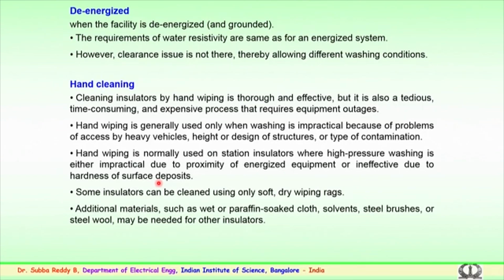So, hand wiping is generally used only when washing is impractical because of problems of access by heavy vehicles, or because of the height or design of a particular structure, or a type of contamination. In such cases hand washing is recommended, and hand wiping is normally used on station insulators, that is, in substations where high pressure washing is impractical, or due to proximity of other energized equipment in the system. So, it will be difficult to completely de-energize the entire substation and take it for maintenance. In such cases, because of the proximity of other equipment nearby the insulators to be cleaned, hand washing is preferred, or where other methods are difficult to use or ineffective due to sometimes the hardness of the surface deposits.